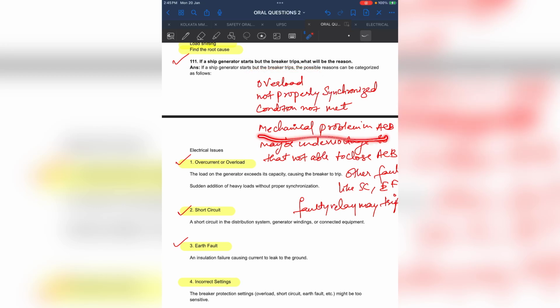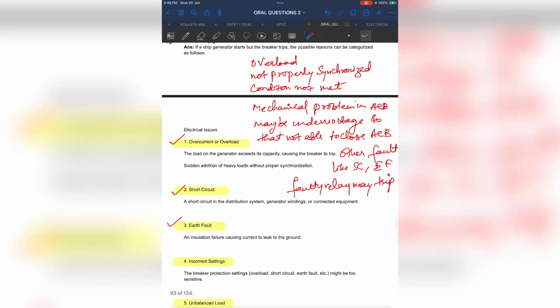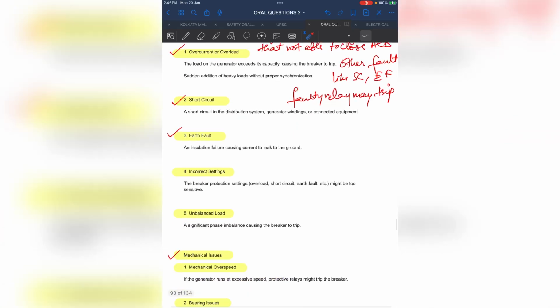Some mechanical problem may also happen in the ACB. There can be an under voltage relay fault, or there may be under voltage, so it is not able to close the ACB. These are basically the chances of the ACB tripping. Other faults, such as some mechanical issue inside the breaker, also need you to open it and check for any damage, which can trip the breaker. So these are basically the chances.